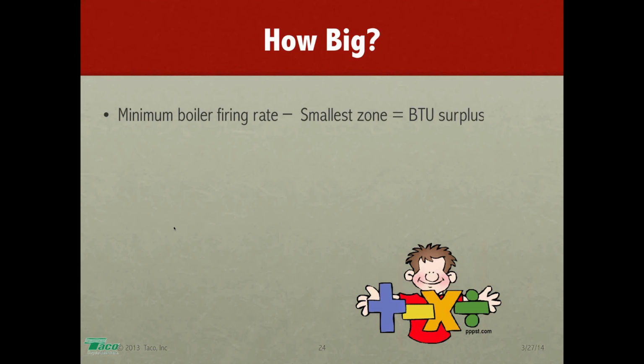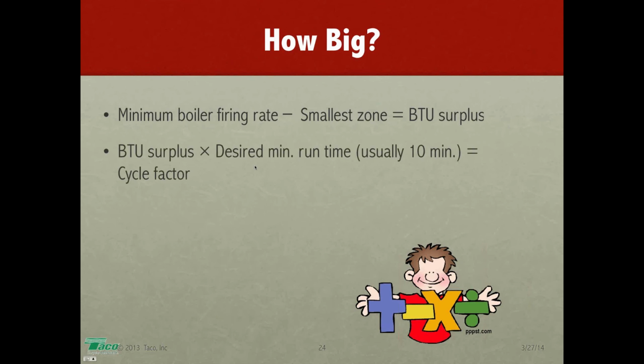The minimum boiler firing rate minus the BTU load of the smallest zone gives you something called the BTU surplus. Next, multiply that BTU surplus by the desired minimum run time of the boiler. Every time it fires, you want it to fire for at least this long, and we usually use 10 minutes. So we have 10-minute burn cycles, nice long burn cycles. We want longer burn cycles, but fewer burn cycles. So BTU surplus times your desired minimum runtime gives you something called the cycle factor.